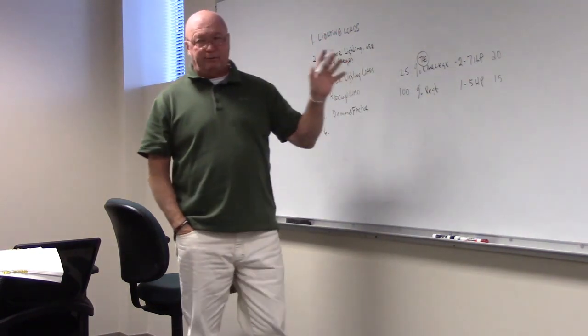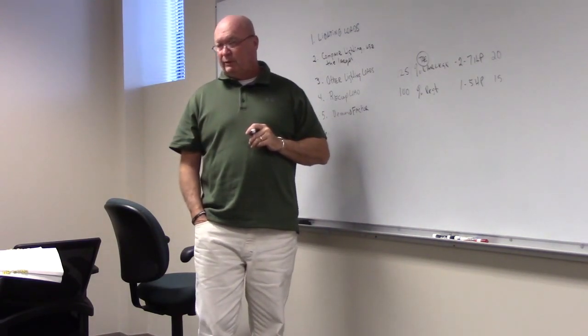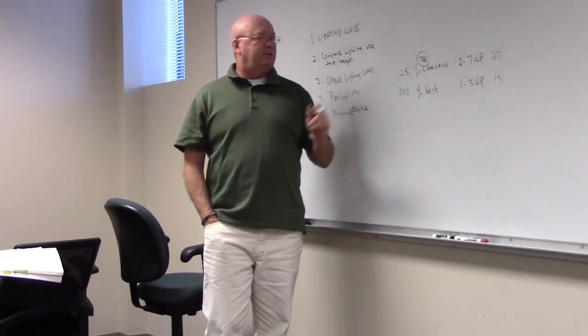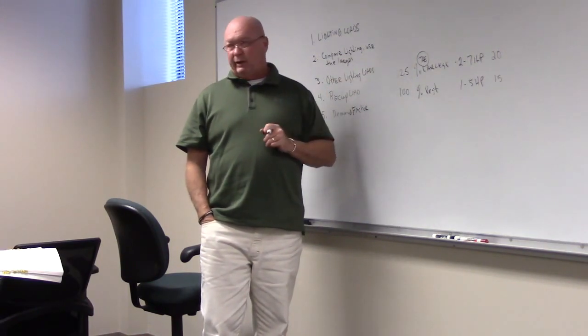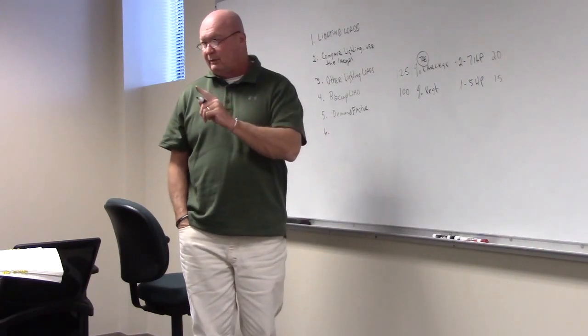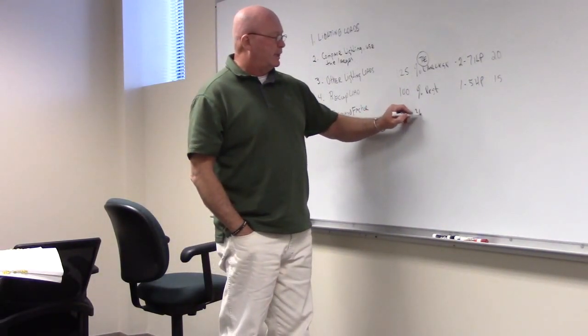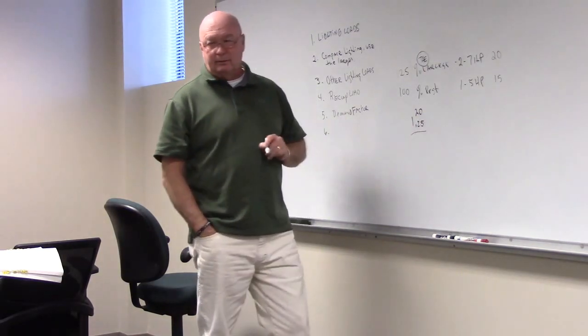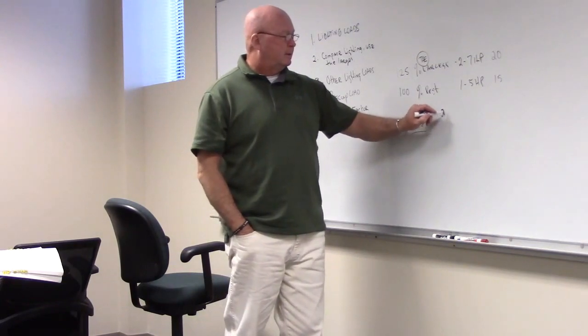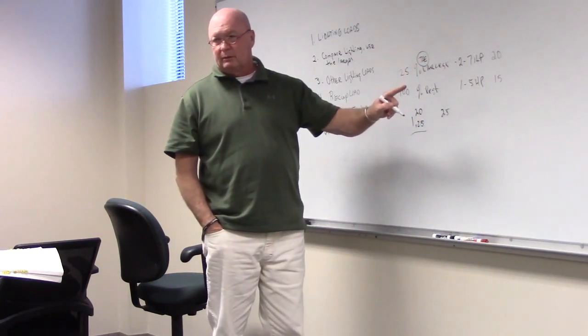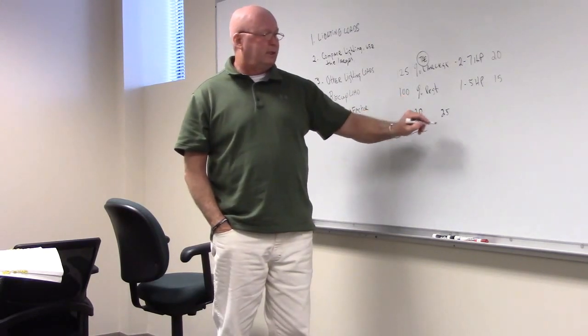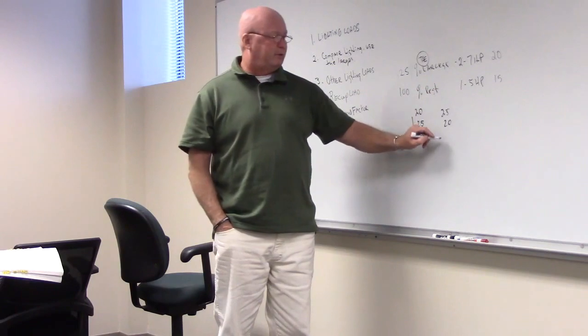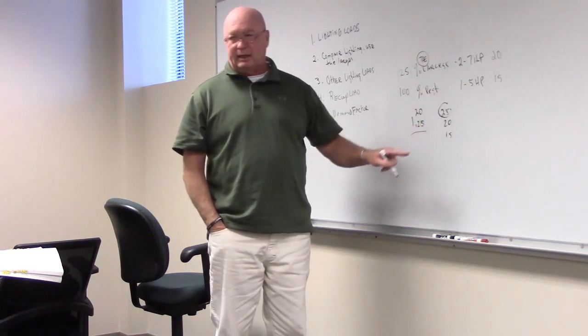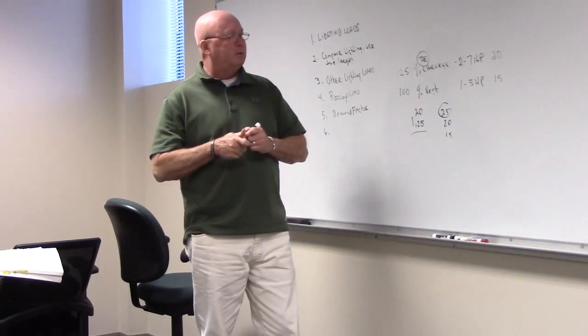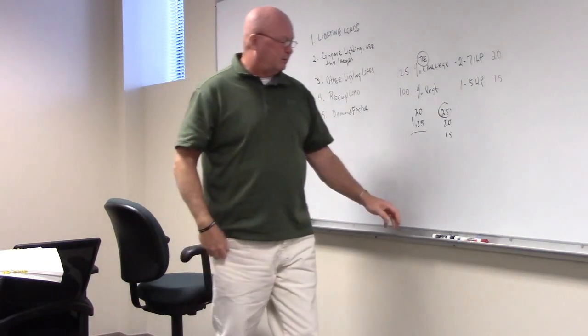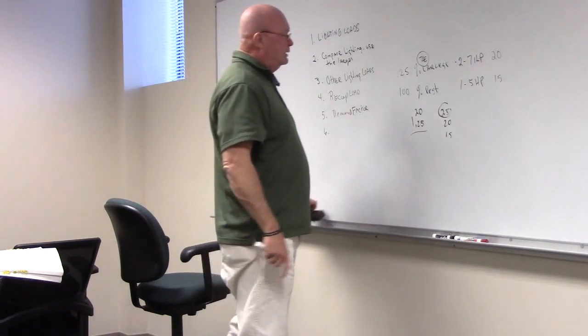What's going to be our total amperage for these 3 motors? What we're going to do is take 125% of what? One 7 horsepower. So we get 20 times 1.25, which is how much? 25. Mm-hmm. And then we're going to add what to it? 20. And then 15. So we wouldn't do this twice, just one motor. Even though they're both the same size, one's 125%, one is not. Very important to remember that right there.